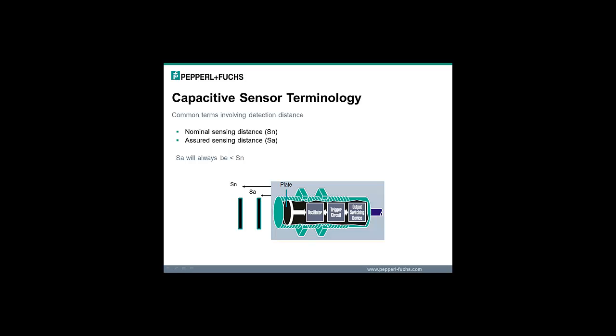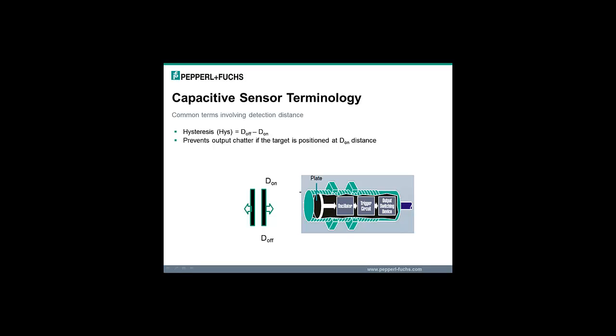Here we see pictorially the difference between the nominal sensing distance and the assured sensing distance. Note that the assured sensing distance will always be lower than the nominal sensing distance. Here we see pictorially the definition of hysteresis. Note that the D, or on distance, is the position at which the sensor changes to the active or on state. When the target is moved away from the sensing face, it will reach a position where the sensor changes to the inactive or off state. The difference between these two distances is defined as hysteresis, and is designed into the sensor to minimize output chatter or instability when the target is at the activation distance.